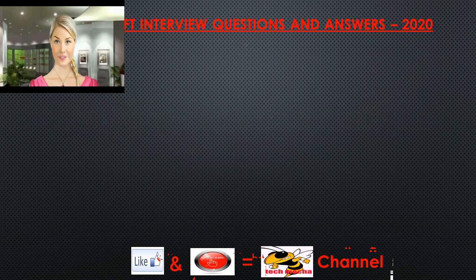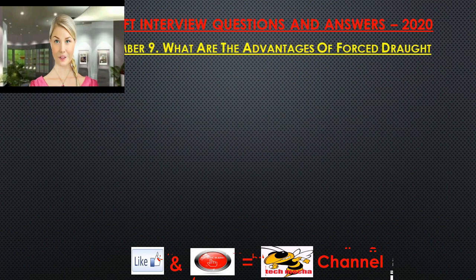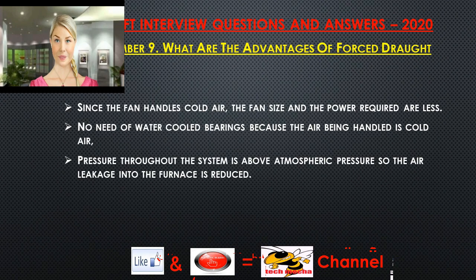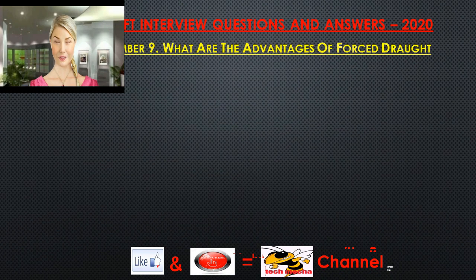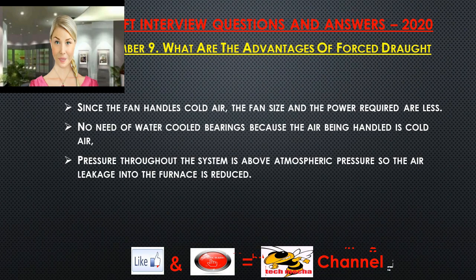Question 9: What are the advantages of the forced draft system? Since the fan handles cold air, the fan size and power required are less. There is no need for water-cooled bearings because the air being handled is cold. Air pressure throughout the system is above atmospheric pressure, so air leakage into the furnace is reduced.